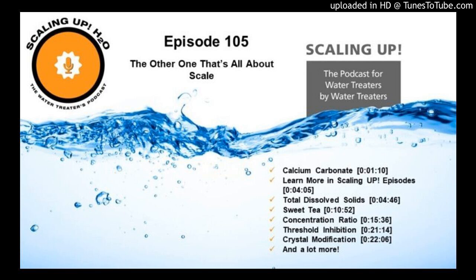So I talked about this a couple of weeks ago, but I'll do it again. As we concentrate, pure water evaporates, leaving its solids behind, and we get to a point where there are so many dissolved solids in the water, we are not able to hold them in solution. Actually, it's the water doing the work. The water cannot hold them in solution, and they create a seed crystal. We call that nucleation, and that crystal begins another crystal, which begins another crystal, and you get this domino effect, and those crystals grow into what we see as scale.